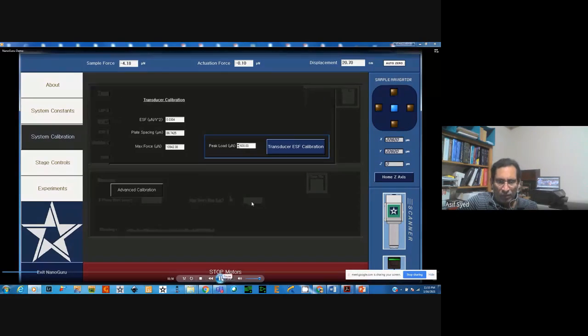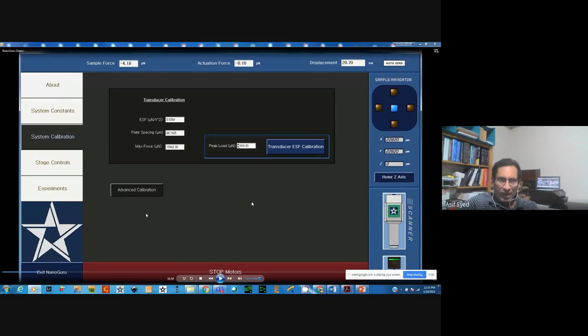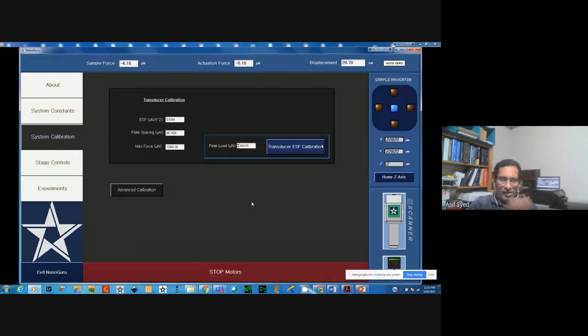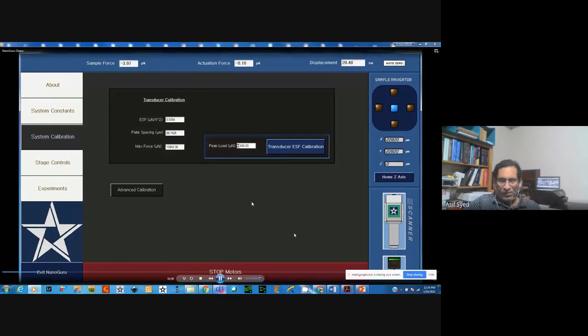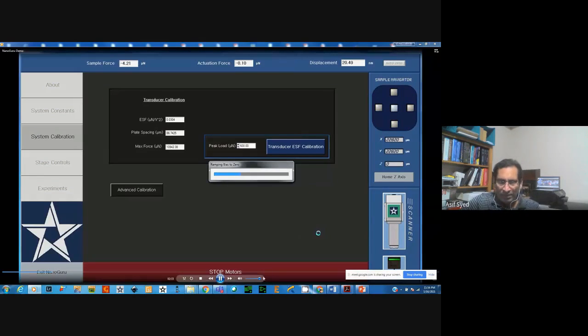When you go to the next button, it opens this interface, and again you can check all these important parameters and make sure they are right. When you click this button, the instrument actuates the transducer and moves the center plate, as I showed in the talk, and measures the displacement response. The center plate is supported by a spring. As you move the center plate, you move the spring, and the spring has a stiffness. Stiffness times displacement is force. We can equate that force to the force generated electrostatically, and with that we calculate the electrostatic force constant. So that is what is being done. When I click the button, it starts the test, and you can see the load displacement curve.